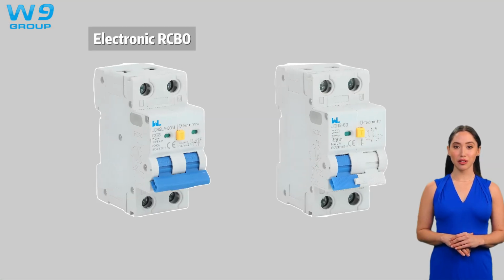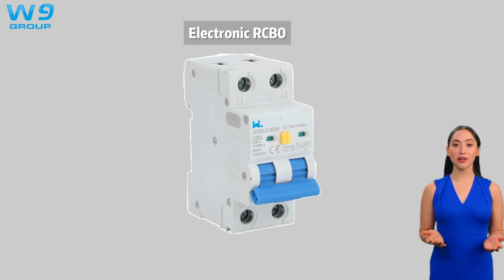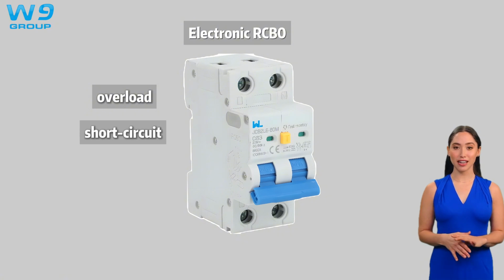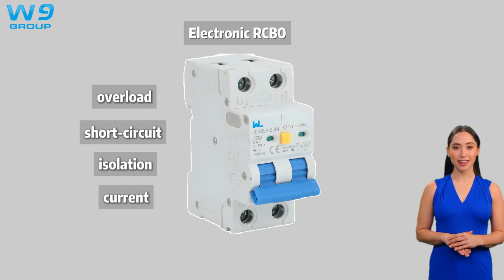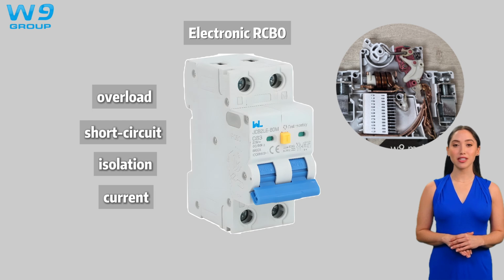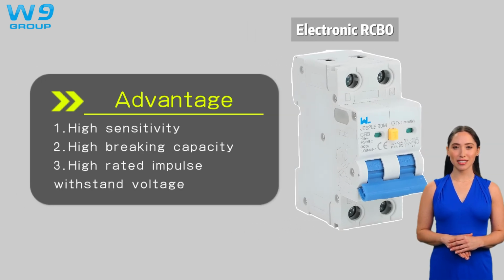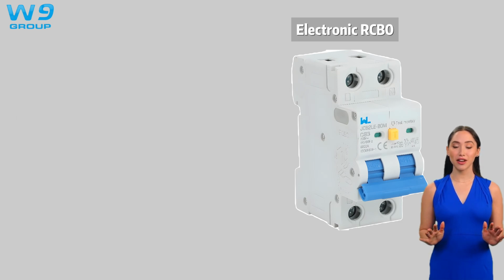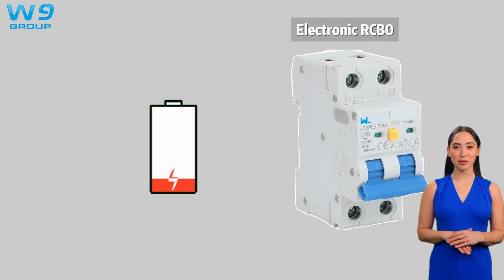RCBO is available in both electronic and electromagnetic types. Electronic RCBO has overload and short circuit protection, isolation and current protection, and relies mainly on electronic components for leakage detection and overload protection. Its advantages are high sensitivity, breaking capacity up to 10 kA, rated impulse withstand voltage up to 6 kV. Although it can respond quickly to small leakage currents, it is functionally dependent on line voltage and needs an auxiliary power supply.